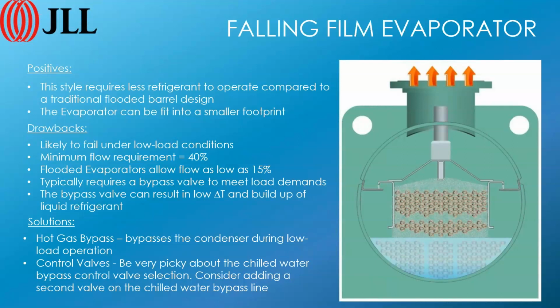Falling film evaporators are more efficient than flooded evaporators for a number of reasons. But the downside is that there's no free lunch in physics. Minimum flow requirement on a falling film evaporator is 40%. So you need to have a bypass line in the chill water loop to make them work properly. Otherwise it won't work properly. If you get down to 10% or 15% flow, you can't run that through this chiller.